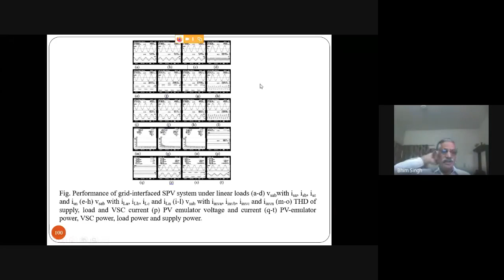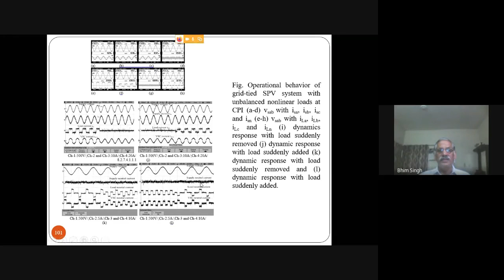And then you can clearly see if you have load unbalancing also, when one phase load is removed, it's able to feed a little more power to the grid because that phase is not consuming the power. And the neutral currents of both the converter fourth leg as well as the load current are changing, so they are exactly opposite, and the grid neutral current is zero. You can see the supply neutral current is almost zero, so you take care of the neutral current compensation also.